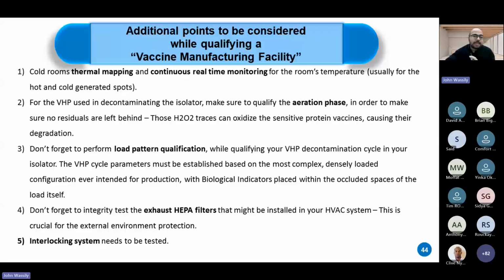Finally, this is a very important slide for you to know. Here we are covering the additional points to be considered while qualifying a vaccine manufacturing facility. You should be covering the cold rooms thermal mapping, the cold rooms that you will be using in storing your vaccines. Also consider continuous and real-time monitoring for the room's temperature, which is usually between 2 to 8 degrees Celsius. And usually we put the temperature monitoring sensors in the hot and cold spots generated from the thermal mapping.